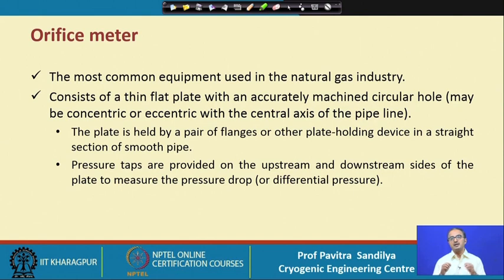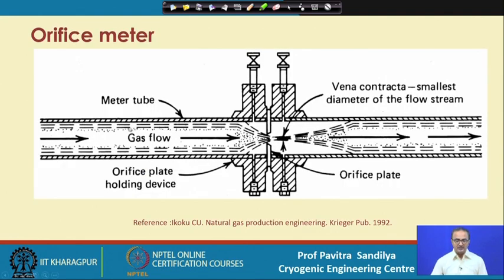Pressure taps are provided at designated locations upstream and downstream of the orifice meter, and all these pressure tap locations have been standardized. The gas flows through the pipeline and through the metering tube, held by a flanging arrangement. As the gas goes through the orifice, the flow converges. The edge of the orifice is not a sharp edge — it is what we call a bevel edge.